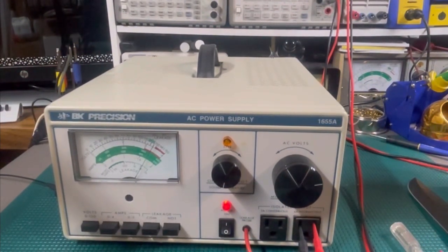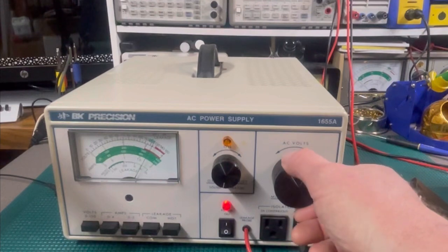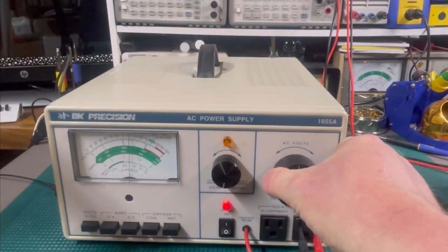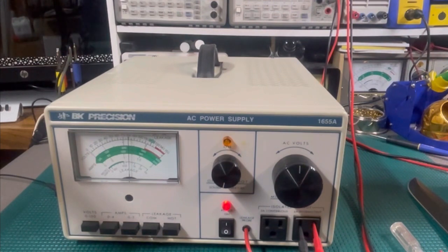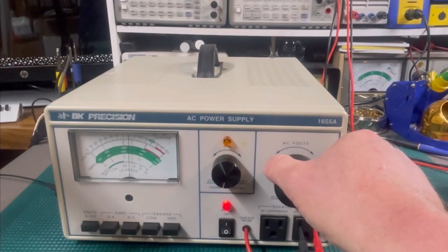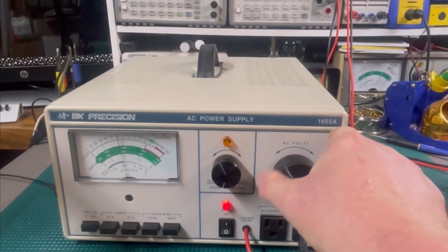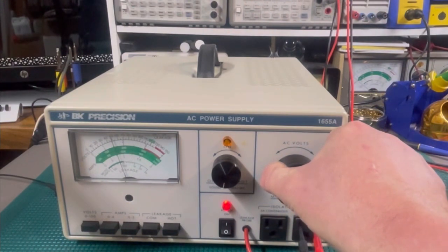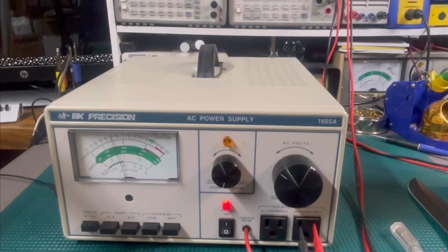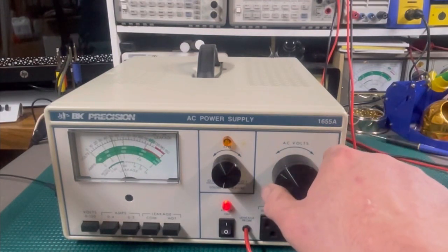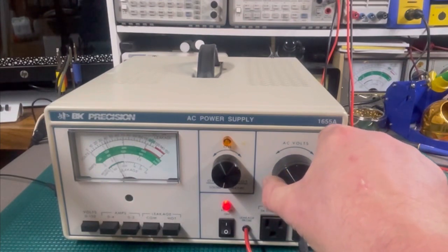Okay, I adjusted the gauge on it the best I could. That's as close as I can get the gauge of it to 120. You see we're 125-ish, but we're dead on 120 voltage coming out. Let's drop it back down to 80. See what 80 reads. 78. So that's pretty darn close right there. 50. 51. Okay, so we're bang on the lower scales.